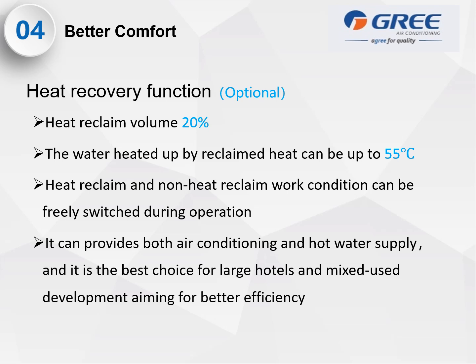For the heat recovery function, this is optional, meaning you can request an air-cooled chiller for dual functionality, meaning heating and cooling. So it can heat reclaim volume for about 20%. The water can be heated by reclaim heat up to 55 degrees C. Heat reclaim and non-heat reclaim work condition can be freely switched during operation. It can provide both air conditioning and hot water supply, and it is the best choice for large hotel and mixed-use development aiming for better efficiency.